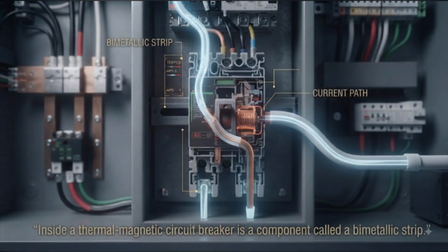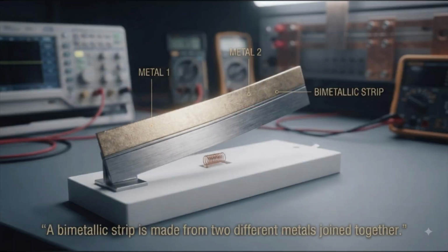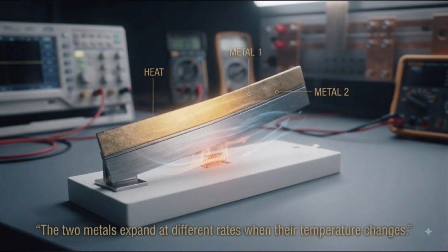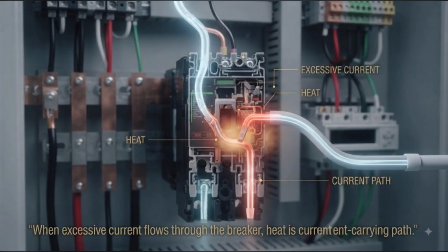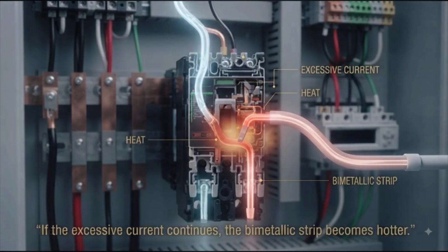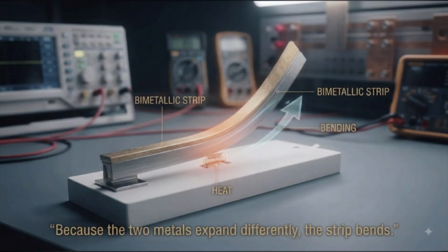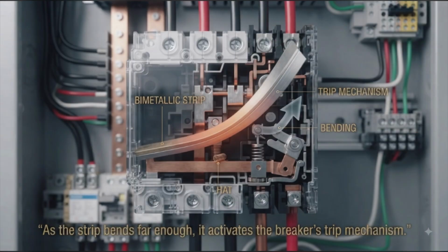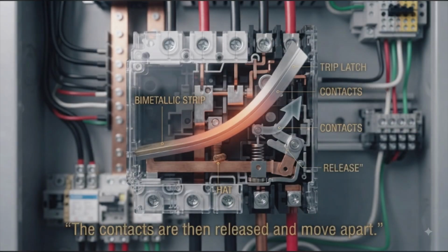The thermal mechanism. Inside a thermomagnetic circuit breaker is a component called a bimetallic strip. A bimetallic strip is made from two different metals joined together. The two metals expand at different rates when their temperature changes. When excessive current flows through the breaker, heat is produced in the current-carrying path. If the excessive current continues, the bimetallic strip becomes hotter. Because the two metals expand differently, the strip bends. As the strip bends far enough, it activates the breaker's trip mechanism. The contacts are then released and move apart.